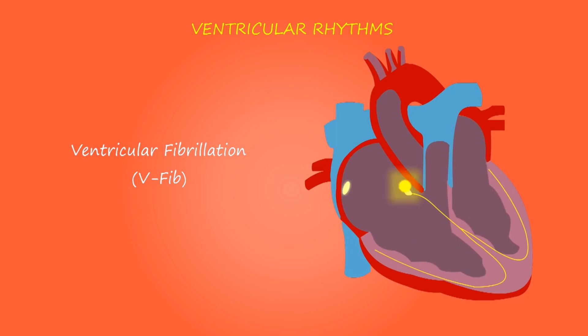A defibrillator shock simultaneously depolarizes a large portion of the ventricular cells so that the fibrillary activity cannot be sustained. This gives a chance for the sinoatrial node, the regular pacemaker, to take over the sequential activation of the heart. Components of a defibrillator. A defibrillator requires a high energy capacitor for storing the high voltage pulse, circuitry to generate and deliver the pulse, an ECG monitor, and electrodes, or paddles, to deliver the shock to the recipient. A battery backup is essential to work the device in case of power failure.